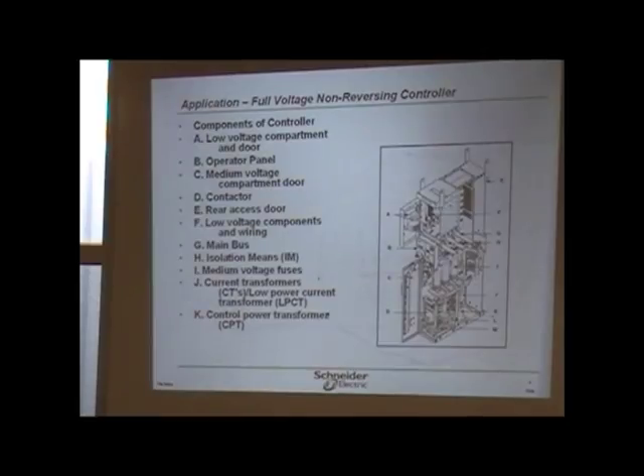Is this like a bucket that you can unlock and pull out of the bus bars? Not a bucket per se. This is on your medium voltage, okay? But it is a little trolley, yes. And what it does is actually house the contactors, so it's a medium voltage non-reversing controller or contactor, because I've got another picture to show this really well.